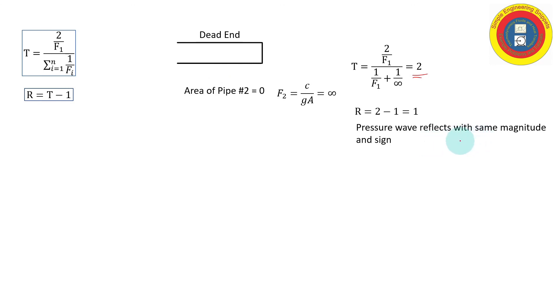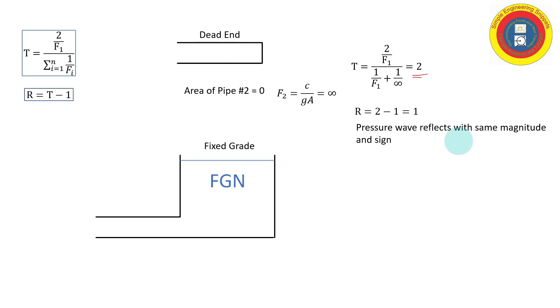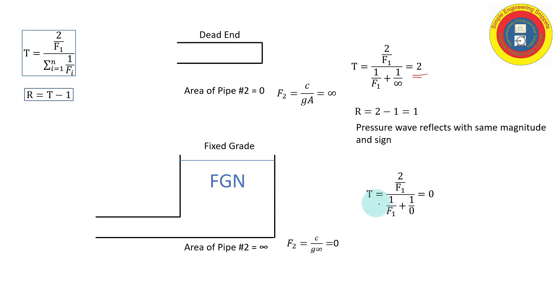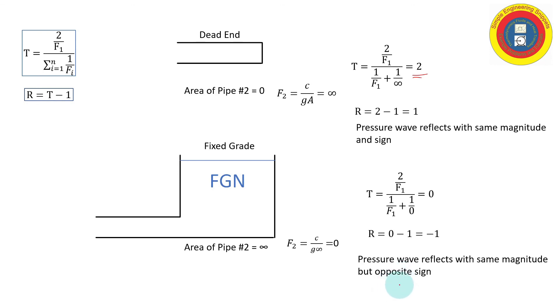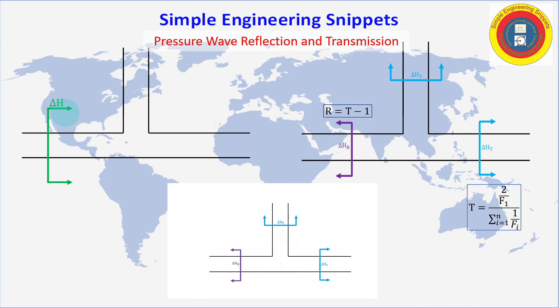For the other extreme — a pipe connected to a very large tank or reservoir (fixed grade node) — pipe two's area is infinity, making its elastic factor zero. One over zero is infinity in the denominator, so the transmission factor T equals zero. The reflection factor R equals negative one: an incoming wave to a large reservoir reflects with the same magnitude but opposite sign.